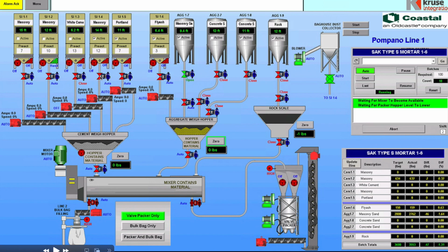So you would put this in manual open, launch this pop-up, and run this motor while you're watching the weight, and then shut this motor off and then shut this off. So now you've added in manually the weight, and then you can hit resume, continue if you had to pause because something didn't work, because something physically in the field jammed, you got a rock in a gate or something like that. So those features are that way.